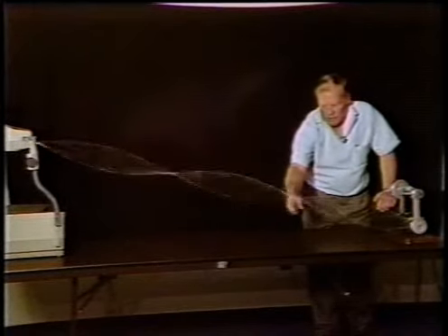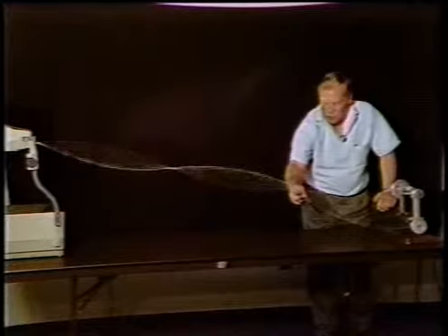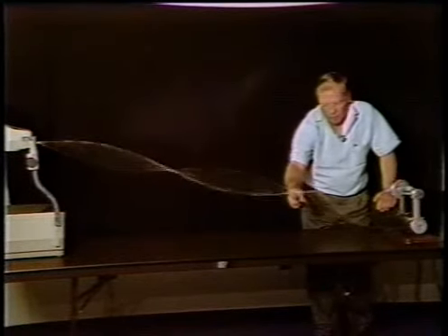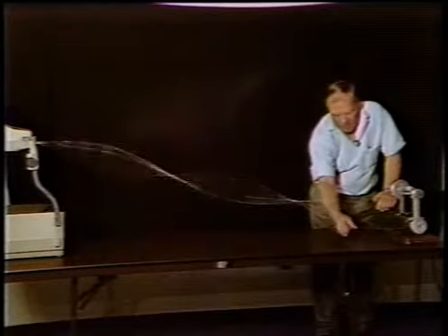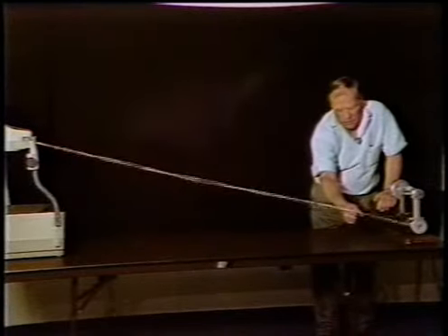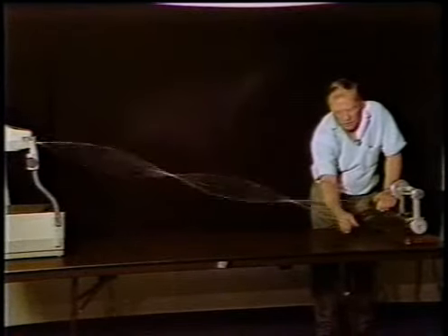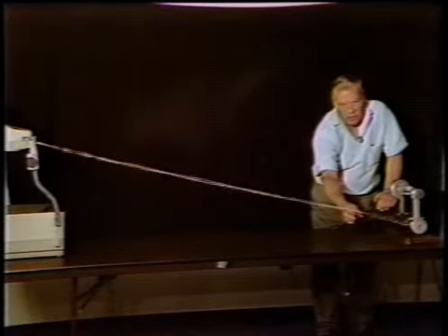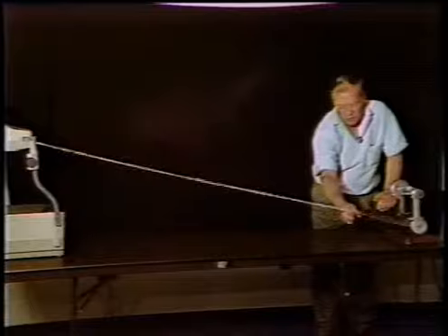As you can see, even a very significant stiffness change at this point really produces very, very little reduction in the vibration. However, let's see what happens if I make a change in stiffness at a point of high vibration, referred to in this case as an antinode. You can see even a moderate stiffness change there produces very, very drastic results.